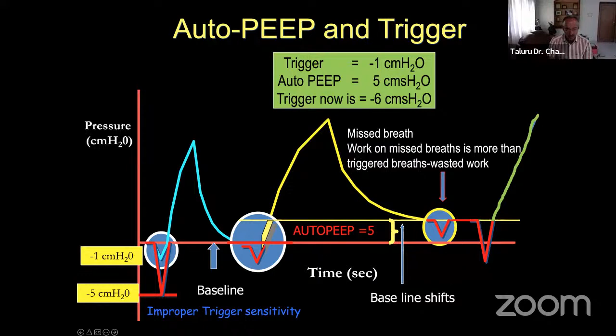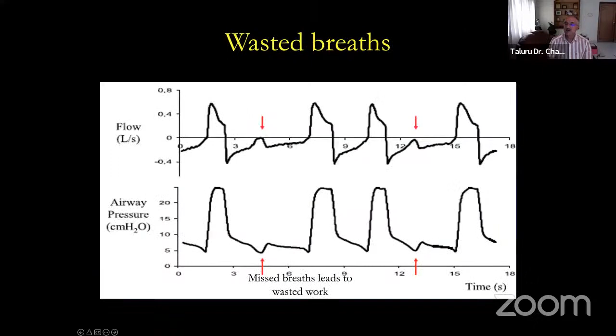You go back and look at your last session where I have given a screenshot of the pressure support where there is an expiratory trigger sensitivity. You can increase the trigger sensitivity from 25%. See, from 25%, if you shift to 50%, the inspiration will get done here only. And if you have shortened the inspiratory time, probably you'll require to increase the rise time or increase the peak flows.